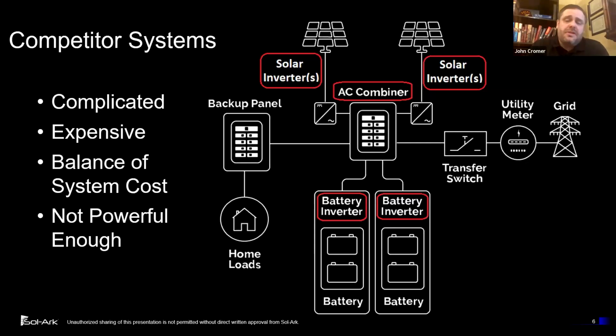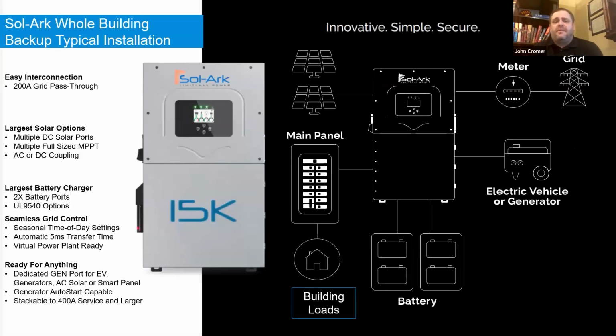So Sol-Ark inverters do tend to be on the pricey side of the inverter spectrum, but that's because it involves all of this additional equipment to get rid of that combiner panel. So you can just put the inverter between, our most popular format is putting the inverter between the grid and the main service panel. And if you have a generator or an EV charger, you can just land them, or what my favorite is, a sub panel. If you have an outdoor panel and an indoor panel, you just land them all directly on the inverter and save time and balance of system material cost.